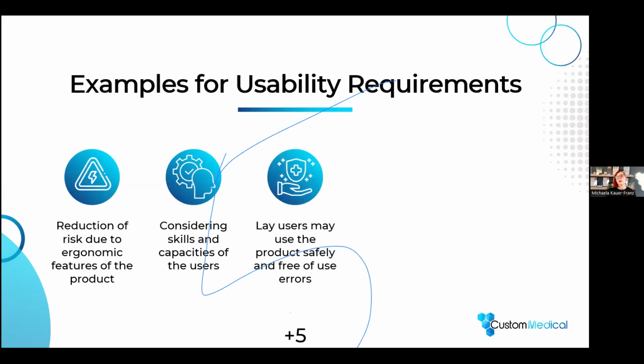Next thing is if you're working with products that are for lay users, you need to make sure that lay users may use your product safely and free of use errors. So that really means you have to show that this is done properly and that somebody who is a lay user is able to use your product. Or one step further, you have to show that your IFU, so the instructions that you have, your labeling, your safety advices, are appropriate for the user groups that you've chosen.